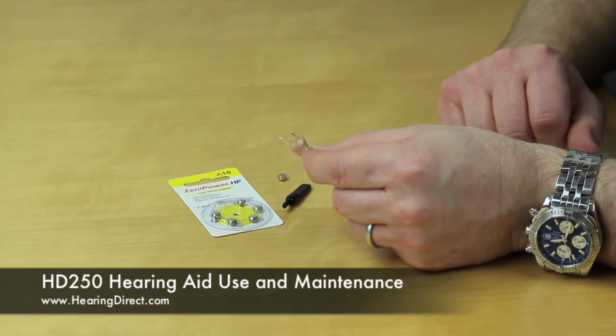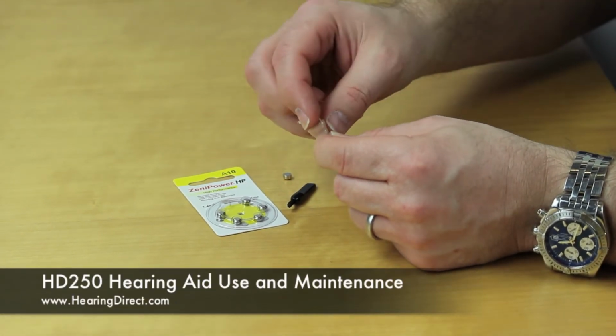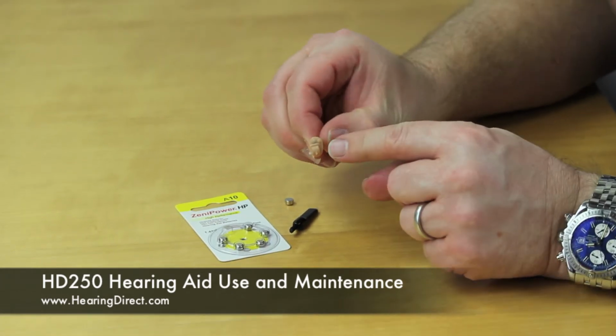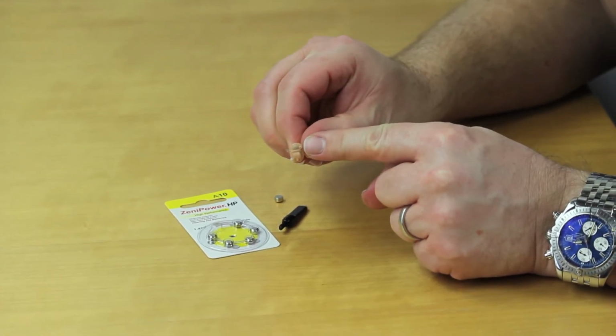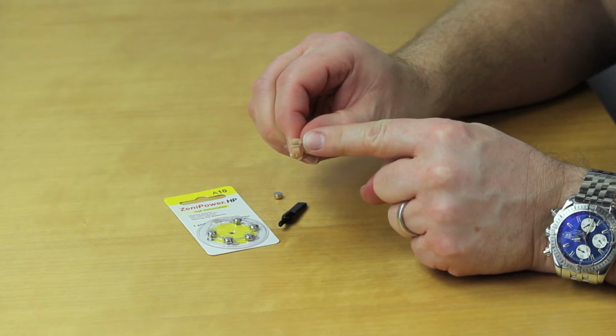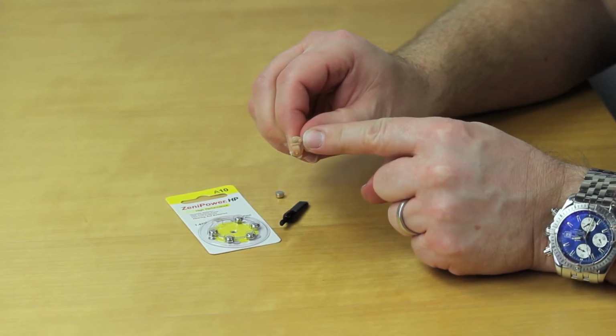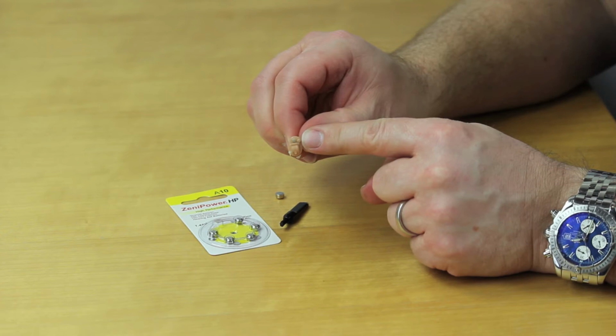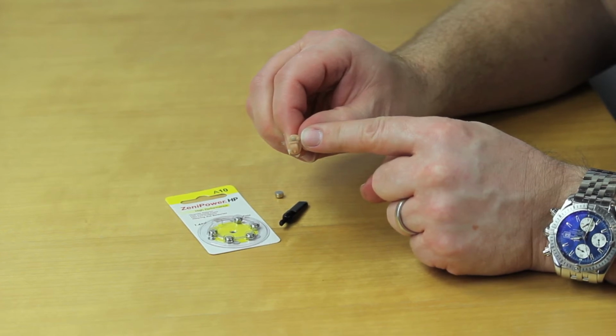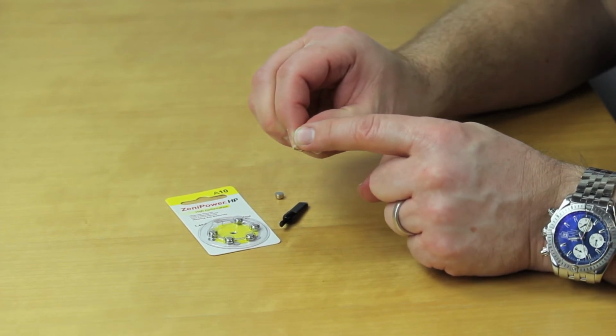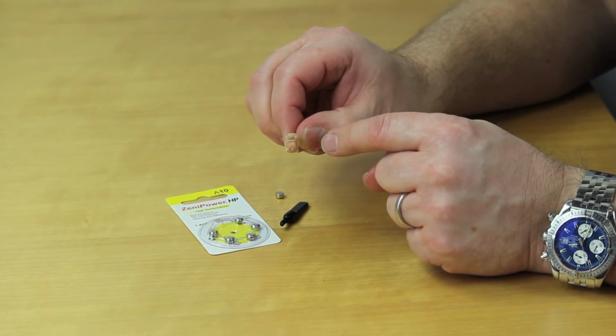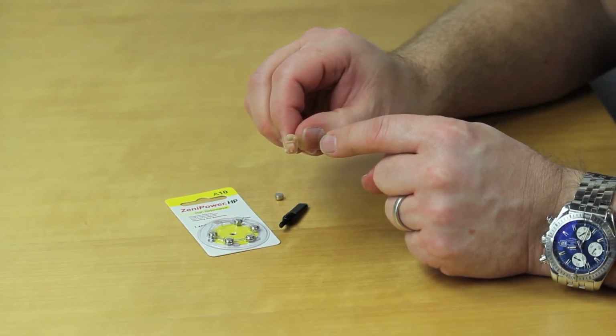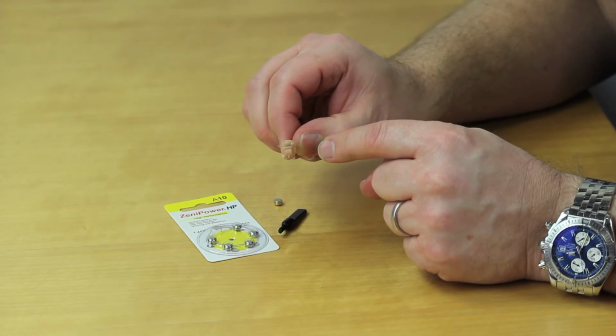In terms of user controls, the HD250 has a push button which has been programmed to act as a volume control. There are 4 different settings. After opening and closing the battery door, the device starts in memory 1. Push 1 time on the push button and the program will cycle up to the next memory. The number of beeps that you hear corresponds to the memory that you have set.